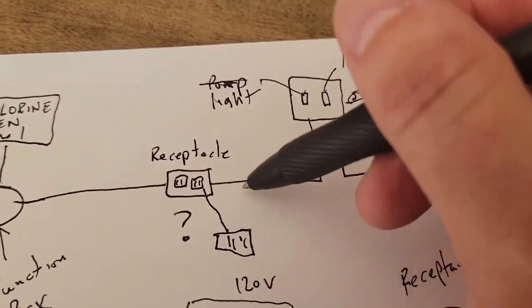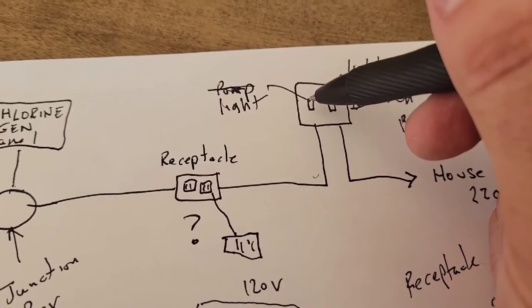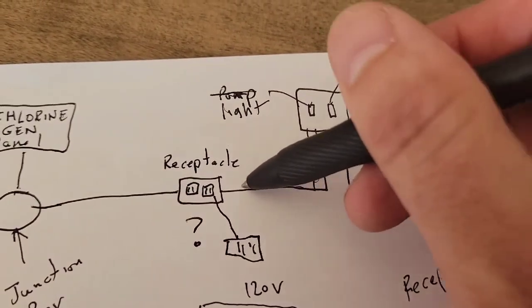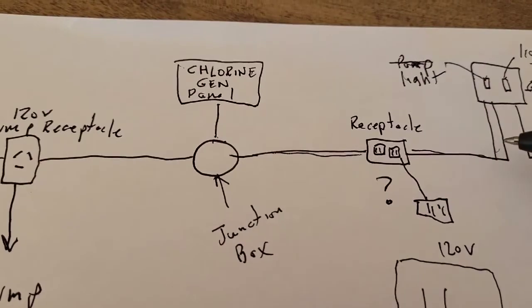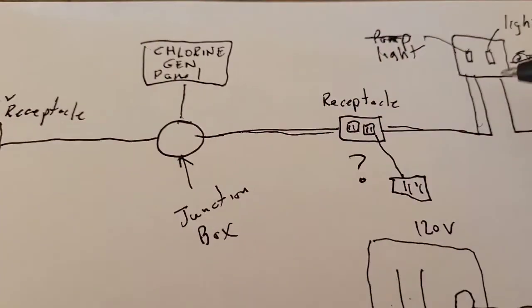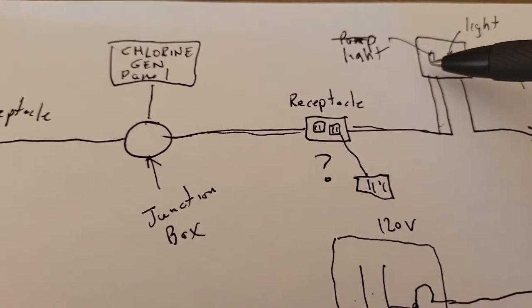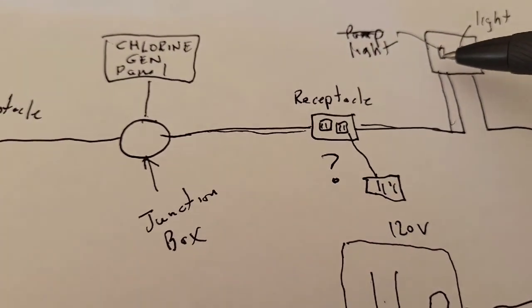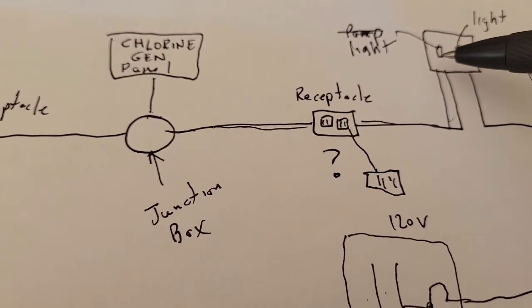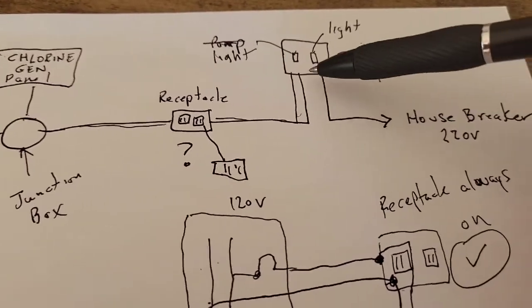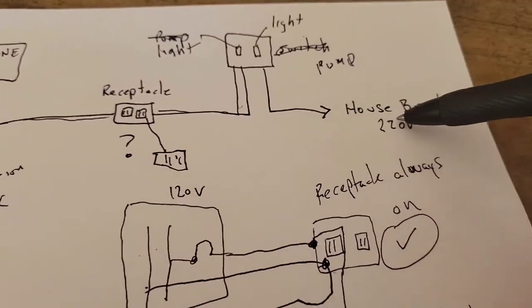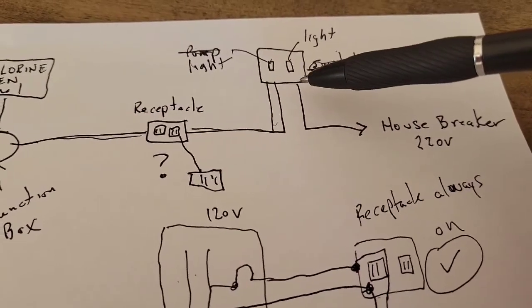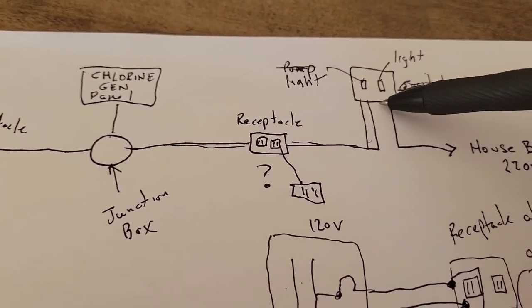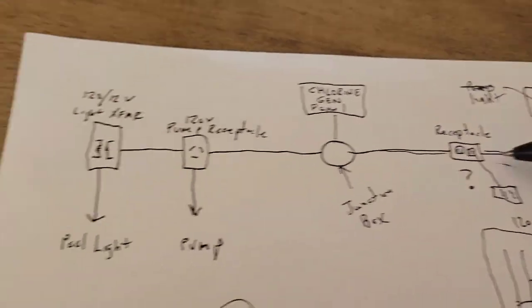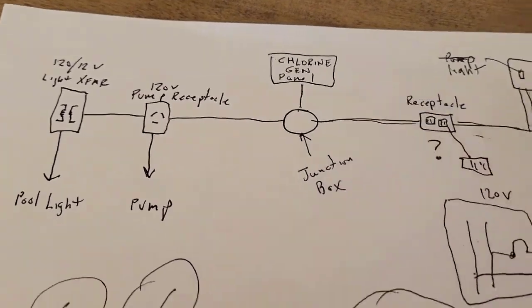The hot lead went to one side of the switch, and the other side of the switch went back down through the conduit to this panel and fed the light transformer separately. So the source for that light transformer panel was this receptacle. The hot lead was fed through this switch in series, and the pump circuit through the 240 volt breaker at the bottom of the breaker panel went through here and then back out through this side and out to the pump receptacle and chlorine generator panel.